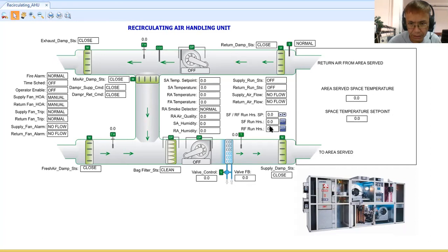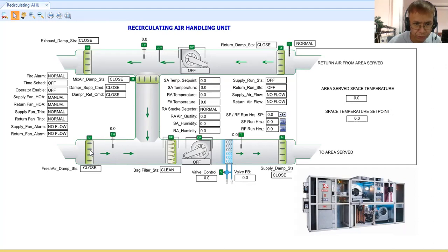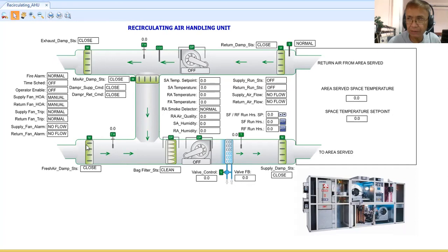The supply and return dampers are open/closed type. The fresh air dampers should actually also be modulating because of a mode called free cooling mode. In free cooling mode, you need to modulate the return damper and the fresh air damper. You also modulate the supply air damper or fresh air damper and the return mixing chamber damper.